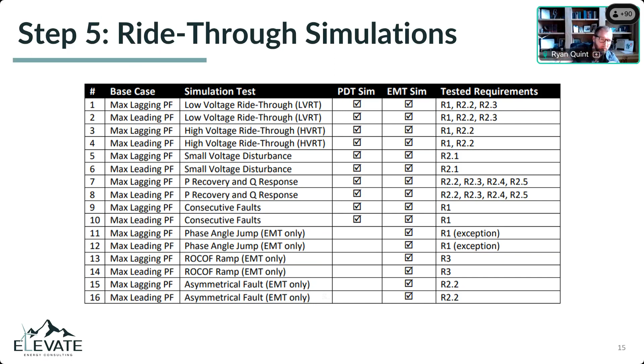Lastly, and I think this is by far the hardest thing, is remediation and corrective actions. You go through the evaluation and determine whether you have necessary software-based updates, protection changes, control setting changes, possibly firmware upgrades or configuration changes, balance of plant relay modifications. Then there's an iterative approach, because you have to create a post-modification state to re-simulate and prove you passed the tests, so you can prepare your final IBR design evaluation and get to work implementing it before operational obligations kick in from a compliance perspective.